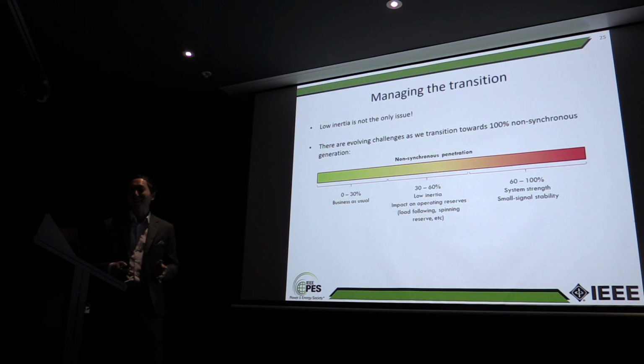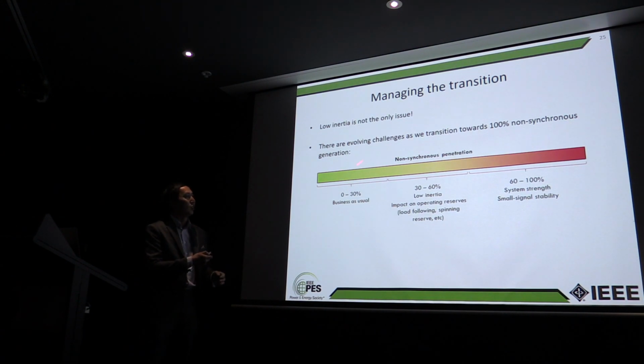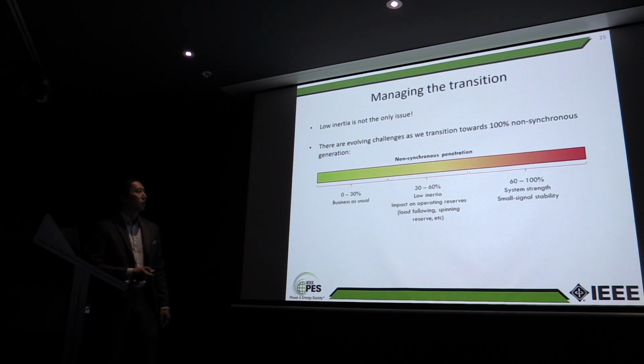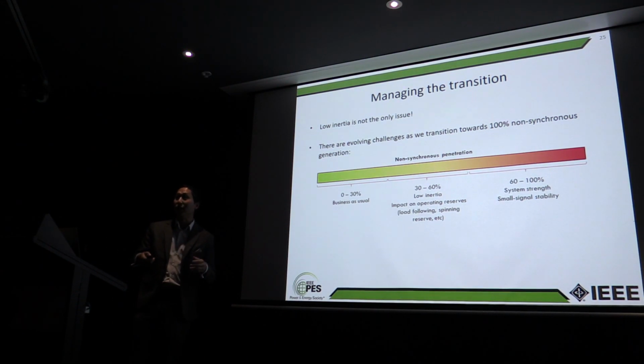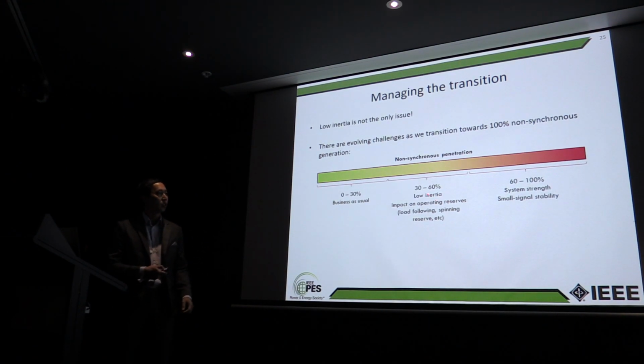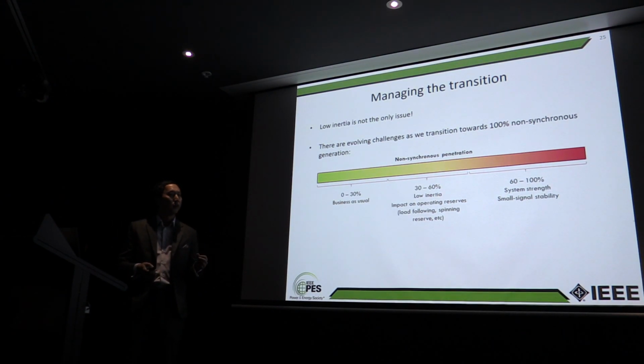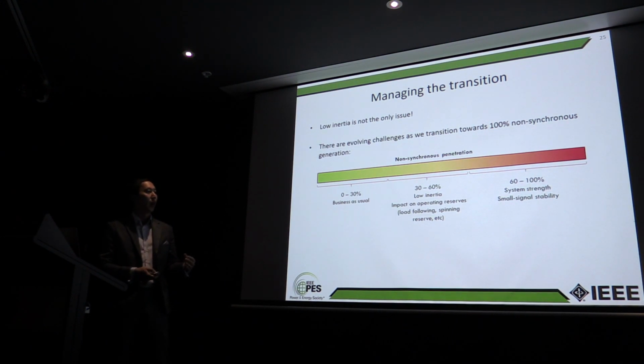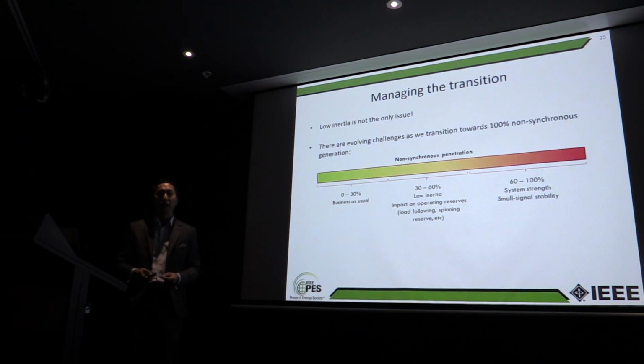Low inertia is not the only issue that we're facing here. As we're getting towards 100% non-synchronous generation, we have a whole set of emerging issues. 0 to 30%, which we're above now, to be fair, was business as usual, but now we're in the 40 to 50-odd percent range instantaneously of non-synchronous generation. That's the area of low inertia, and it has an impact on our operating reserve. So how we manage the system is we add more spinning reserve, we have more load following, we do all those kinds of things.